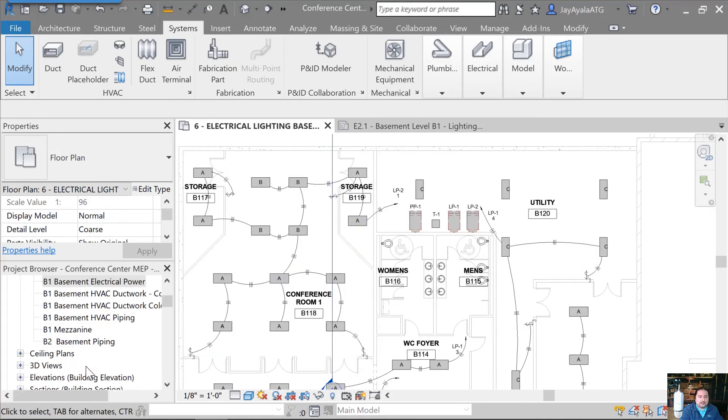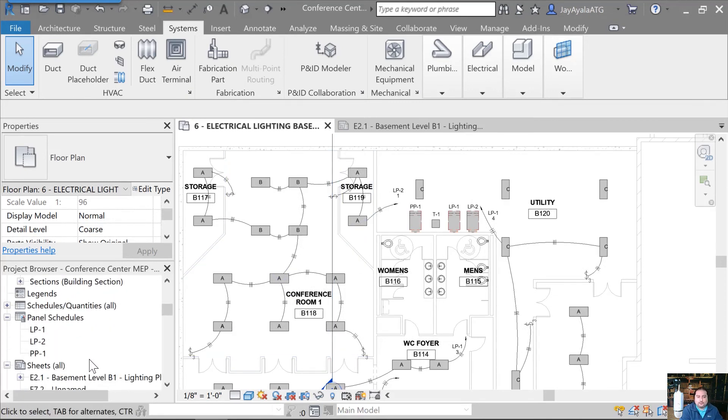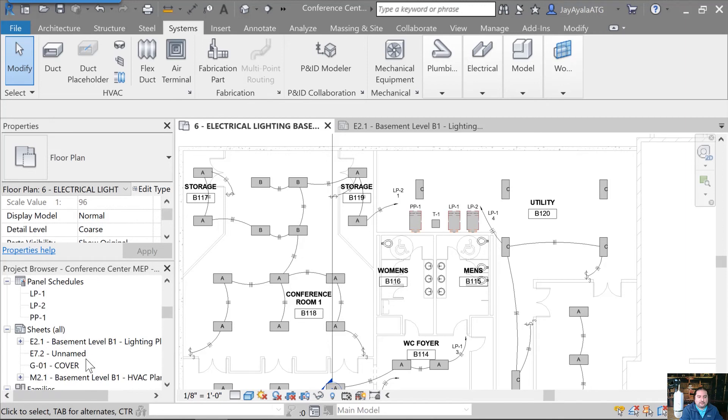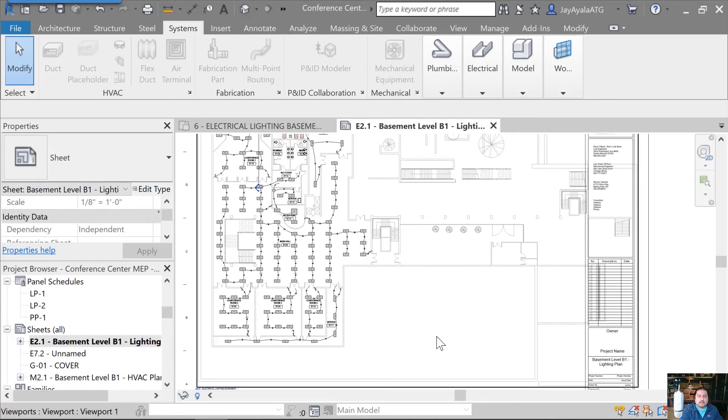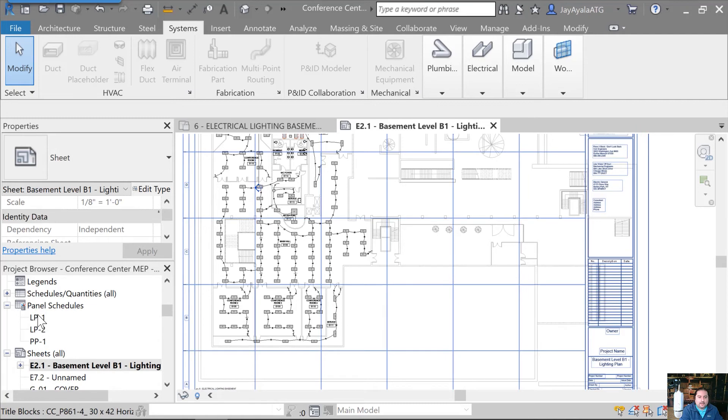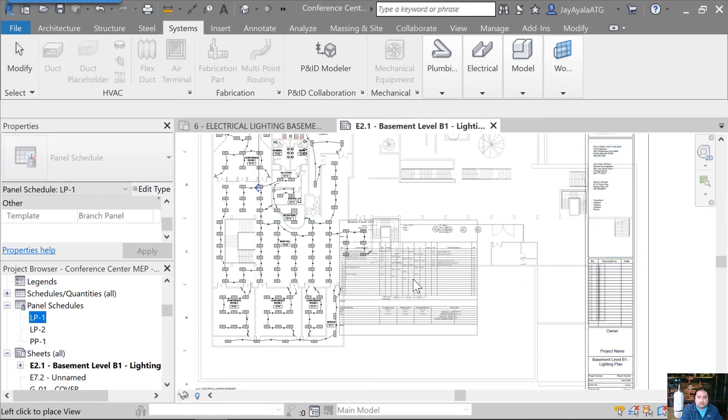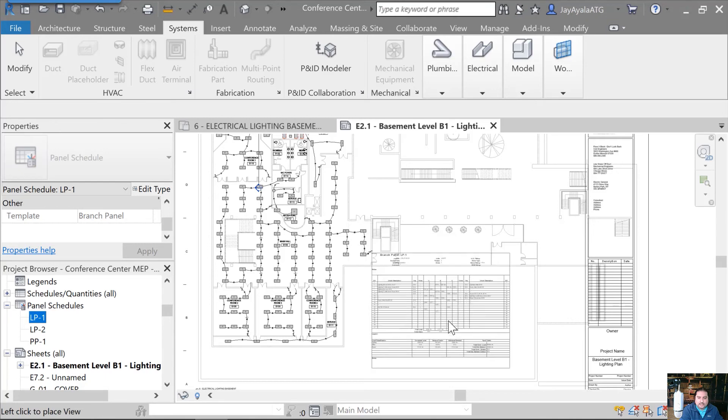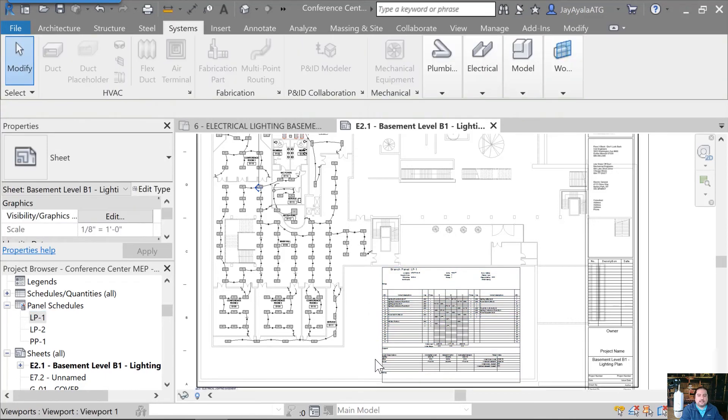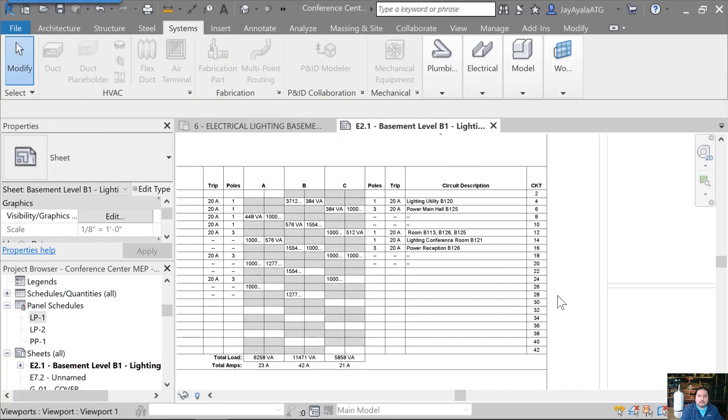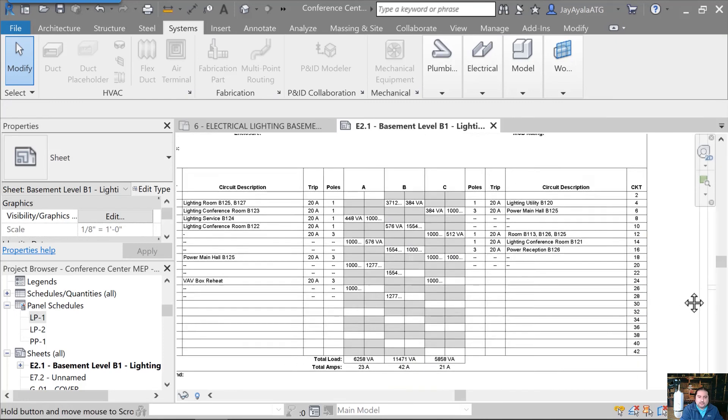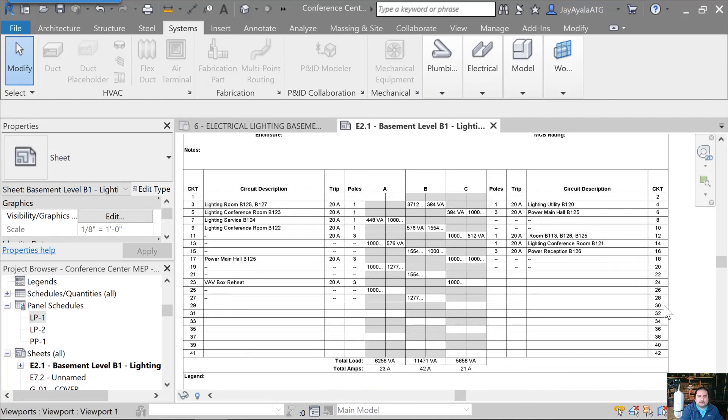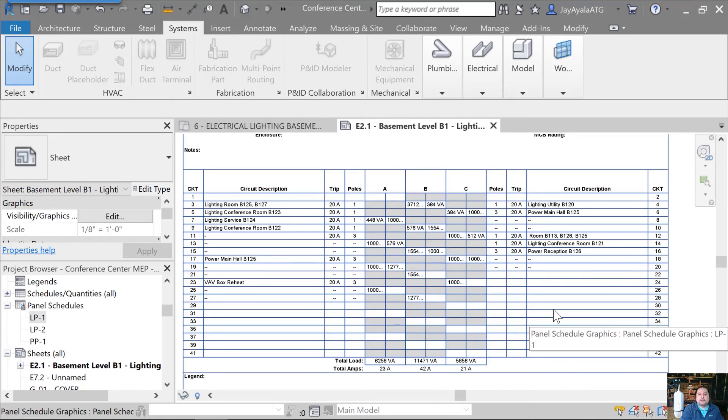And when I add the wiring yet again, it doesn't redo the wiring that I've already modified or the home run, it just automatically does that. So, one of the final things I want to show you, which was one of the most important things, is to document this easily. I can simply go grab the lighting panel number one, for example, the one that's more mature and has more lighting fixtures, and I can place that on my sheet. Now that lighting panel is bi-directional, right? So if I start modifying it here, or if I start modifying it in the floor plans, this will keep up to date.